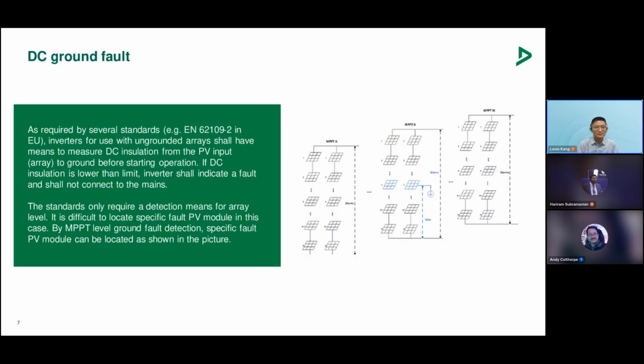As required by many standards, inverters for use with ungrounded arrays should have means to measure DC insulation from the PV input to ground before starting operation. If DC insulation is lower than the limit, the inverter should indicate a fault and should not connect to the mains. When the ground fault happens, the maintenance person can see the fault signal and will try to localize the fault PV module. In a utility-scale PV power plant, the increasing power of PV inverters and the increasing number of PV strings make such troubleshooting more difficult and time-consuming than in a distributed power plant.